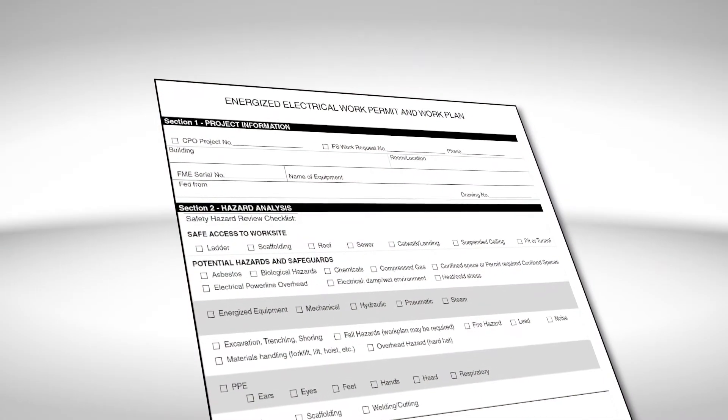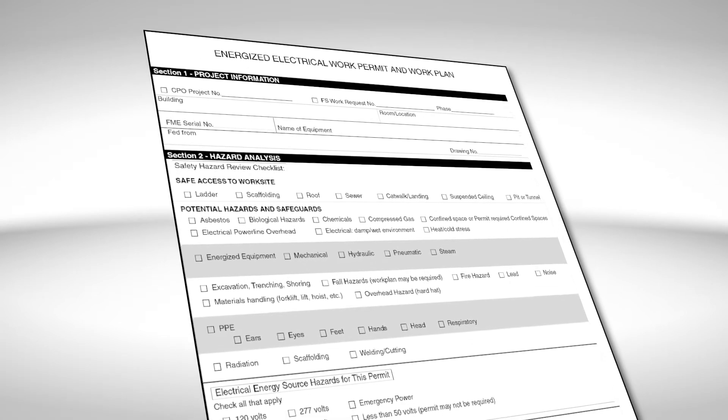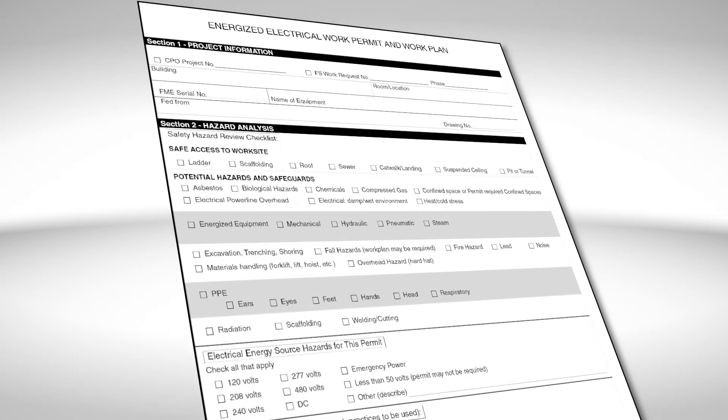Both OSHA and NFPA 70E require that work be performed on de-energized equipment. However, if your employer can show that the task you need to perform is infeasible in a de-energized state, the work can be done on the energized unit. In this case, an energized electrical work permit may be required.